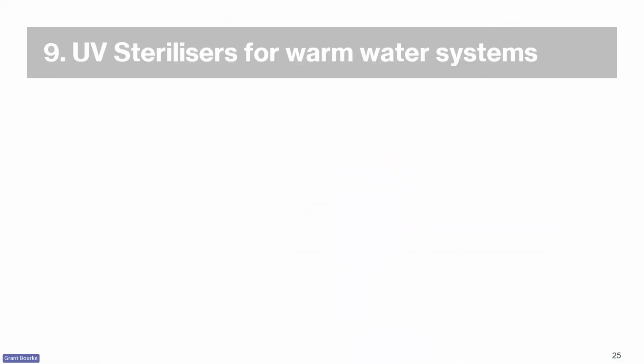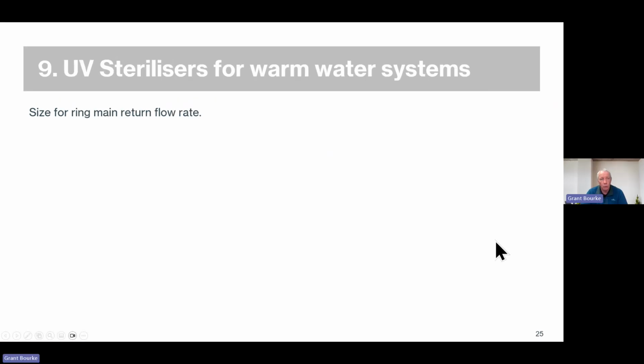So let's have a look at UV sterilizers on those warm water systems. So we size it for the ring main return flow rate. Now, if you have a bigger pump, you're going to need a bigger sterilizer. So if you size the sterilizer and it was close to the ring main flow rate, and some genius decides to put a bigger pump in, you need to put a bigger UV sterilizer in potentially.